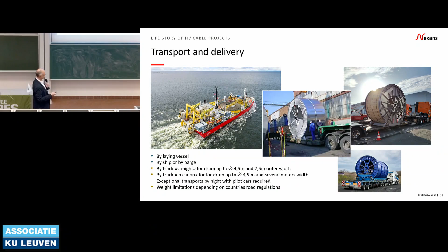After that, you have to install it. You're not yet in the operational phase. You have the laying vessels to install the cable, and via the ship we unroll the cable directly into the sea. When the cable arrives on the seabed, we use remote vehicles that open the trench at the bottom of the ocean to protect the cable, by jetting. It's a hydrojetting process that opens the trench and then closes it afterwards to protect your cable. Then we can put concrete slabs, when necessary, on the cable to protect it from damage.